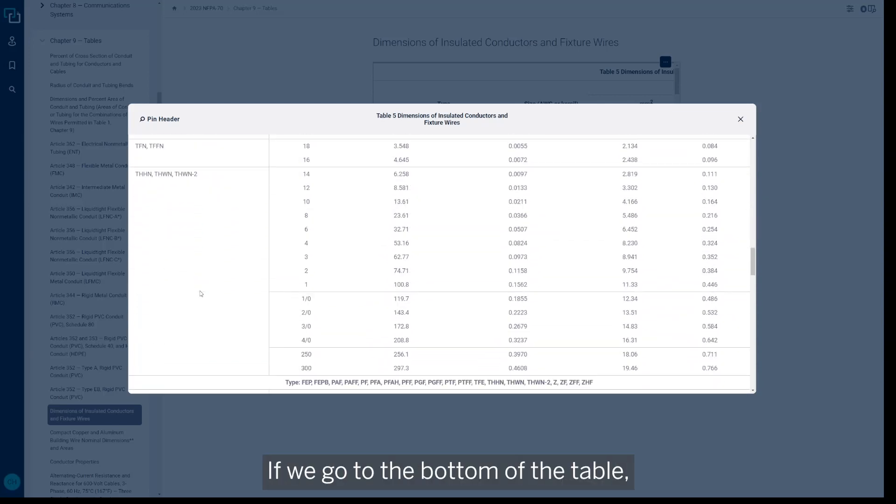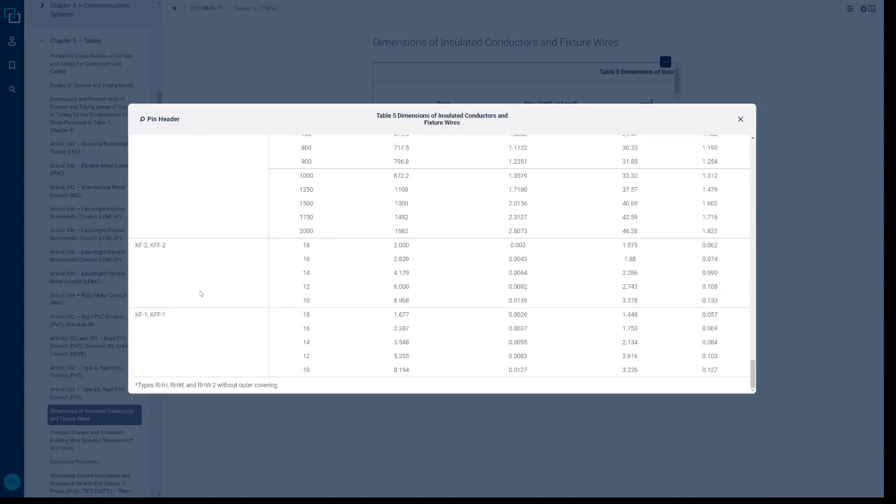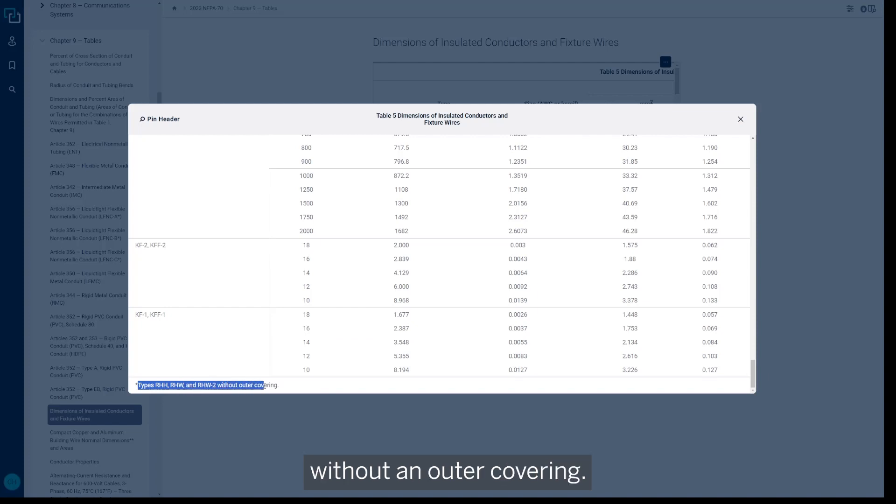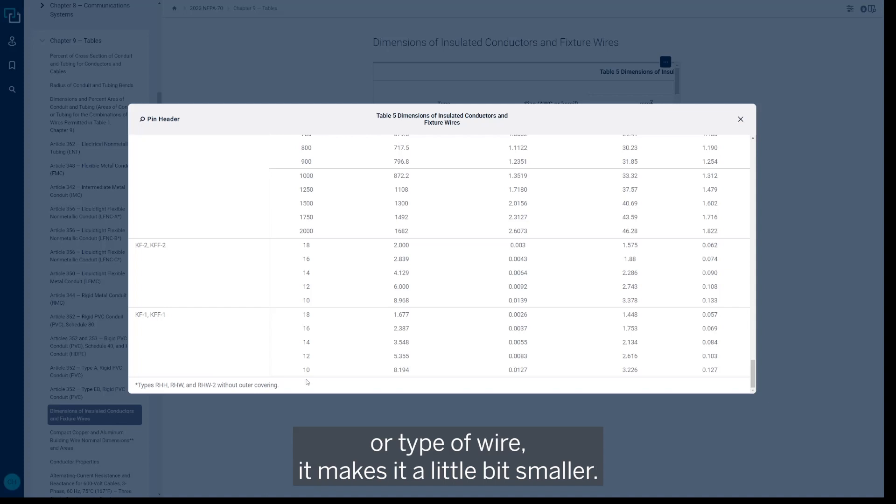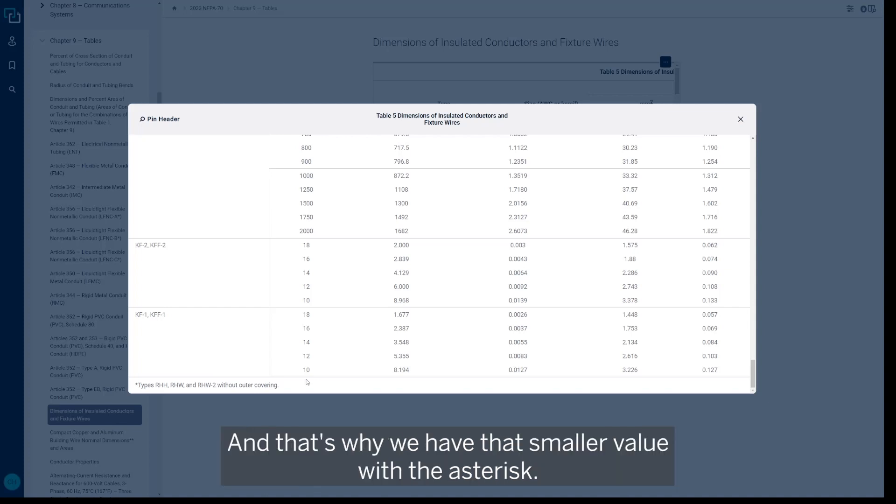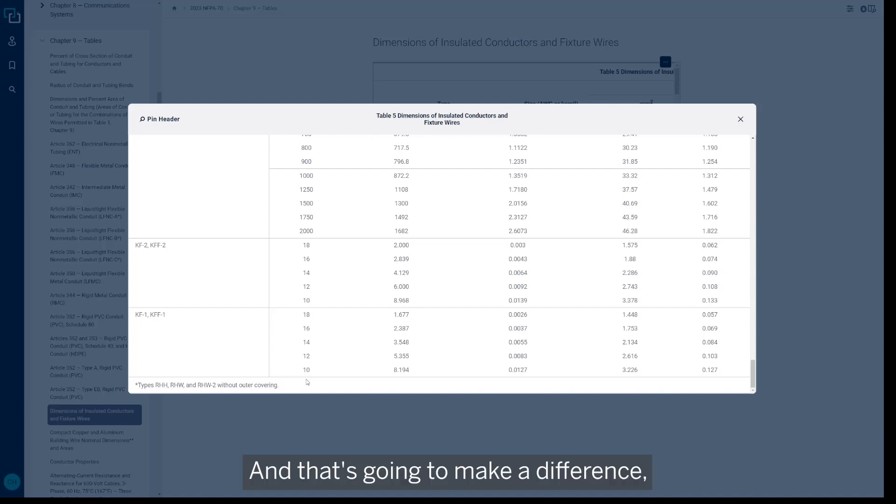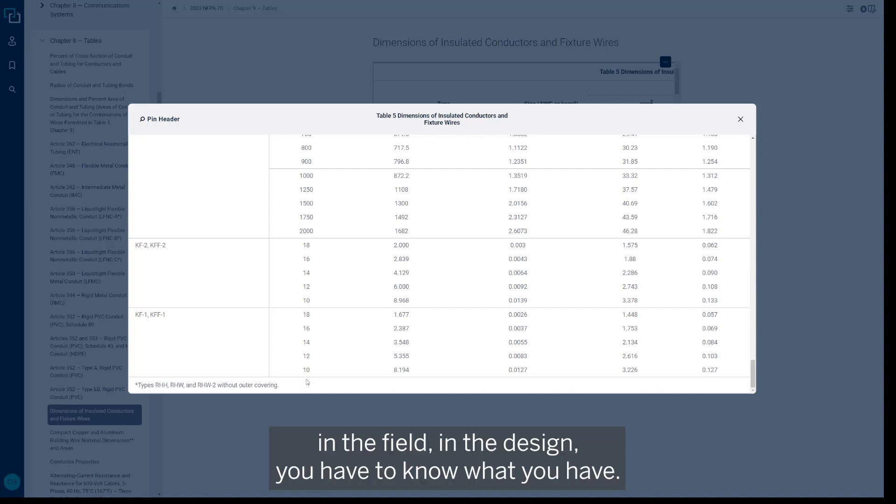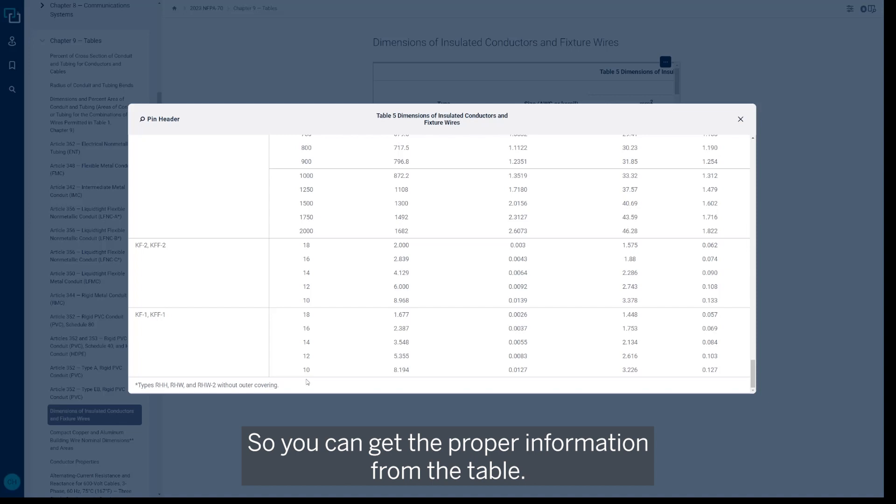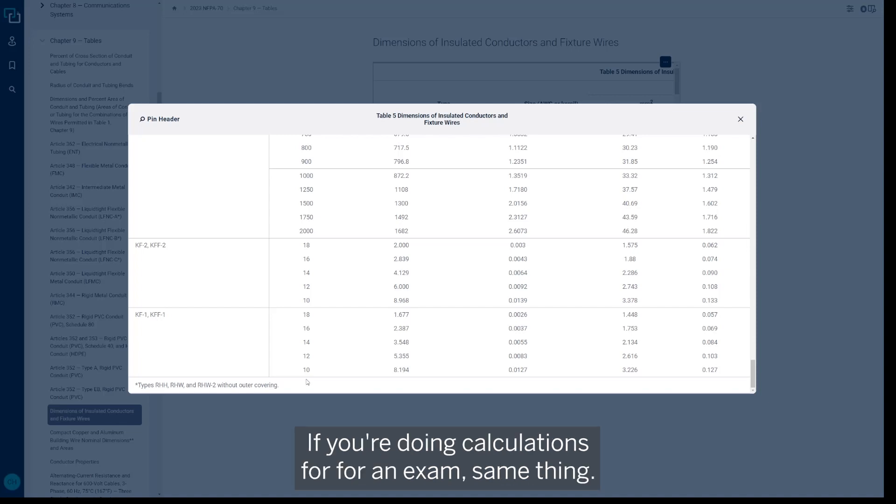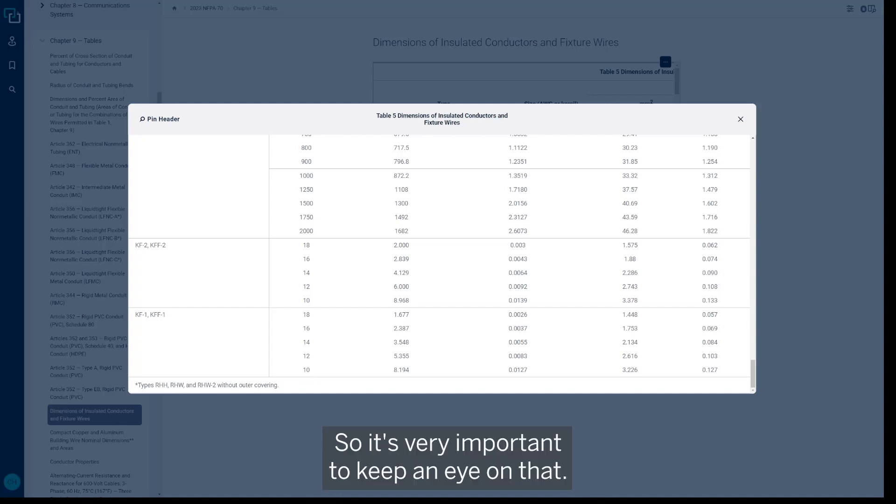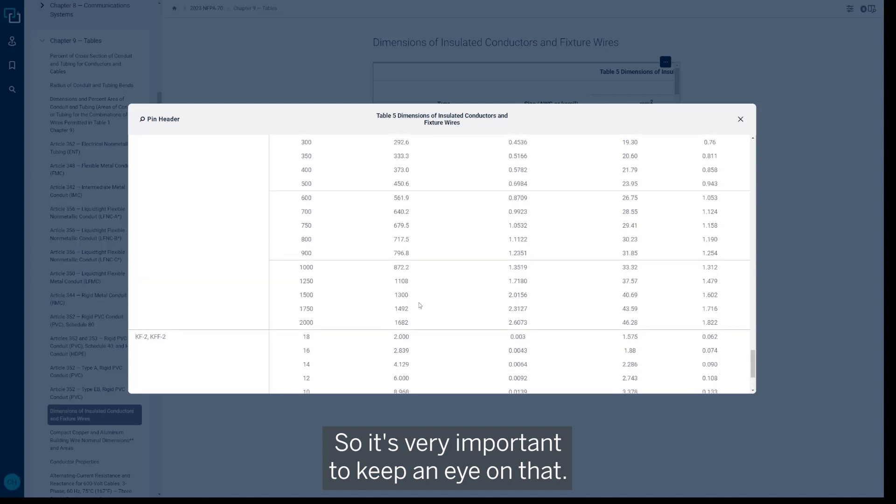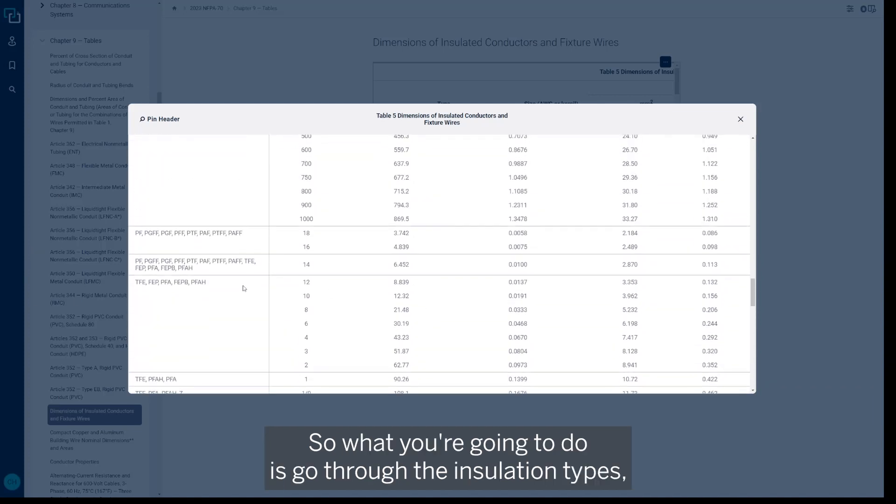If we go to the bottom of the table, it tells us types RHH, RHW, and RHW-2 without an outer covering. So with not having the outer covering for this specific type of insulation or type of wire, it makes it a little bit smaller, and that's why we have that smaller value with the asterisk. So that's going to make a difference, you know, in the field, in the design—you have to know what you have so you can get the proper information from the table. If you're doing calculations for an exam, same thing—you want to make sure you get the right information. So it's very important to keep an eye on that.